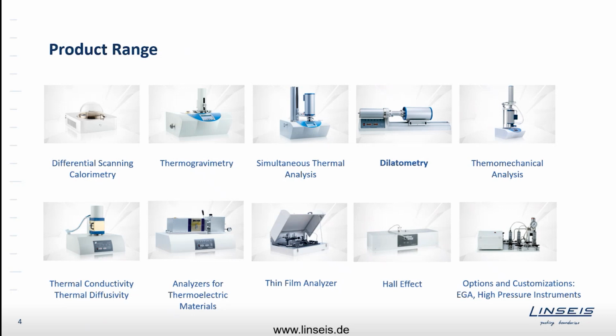in different shapes for a complete range from liquid nitrogen temperature up to 2400 centigrades. They can also be combined with thermobalances, the next product in line. So thermobalances is also a typical classical instrument where you can measure the weight change of a sample during heating, during cooling. And the combination of DSC and thermogravimetry would be a so-called simultaneous thermal analysis.